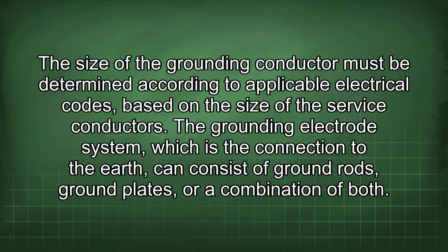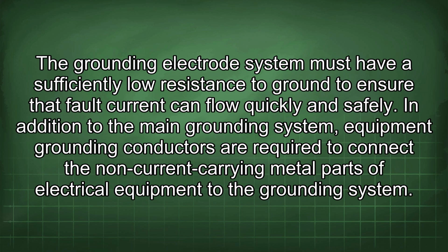The grounding electrode system, which is the connection to the earth, can consist of ground rods, ground plates, or a combination of both. The grounding electrode system must have a sufficiently low resistance to ground to ensure that fault current can flow quickly and safely.